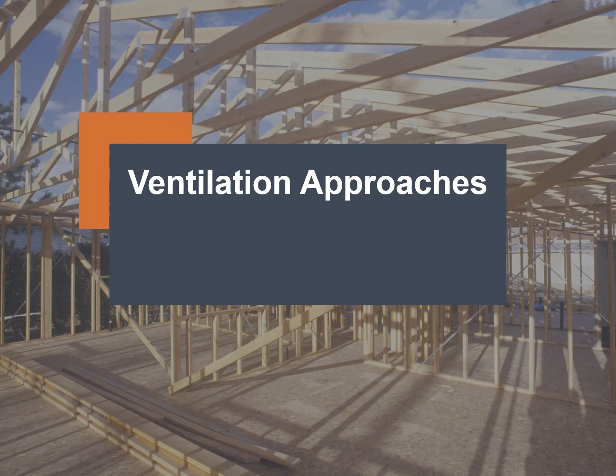The first is, in order to get the ventilation components, it's not actually in the International Energy Code or the Washington State Energy Code. It's actually in the Washington State amended version of the International Mechanical Code. For multifamily or R2 buildings, this now requires balanced ventilation or balanced airflow, which means the same amount of air that comes in is the same amount of air that goes out within 10% or 5 cubic feet per minute of air.